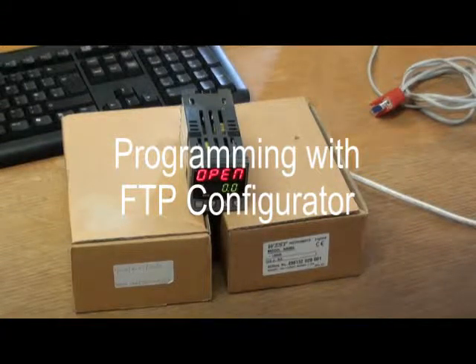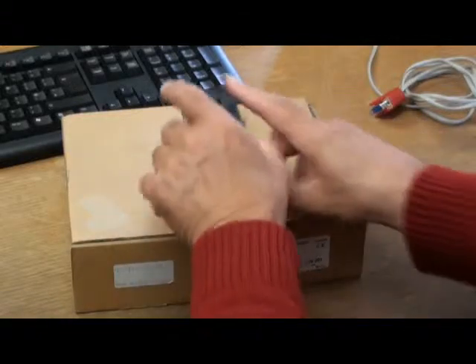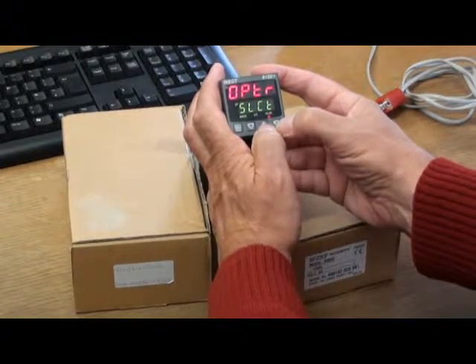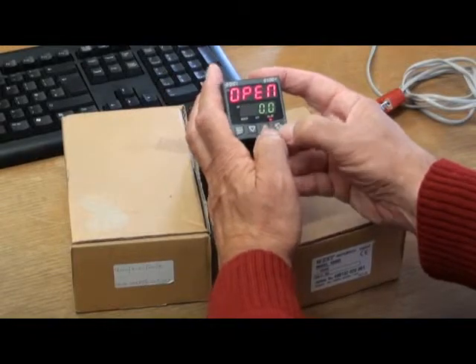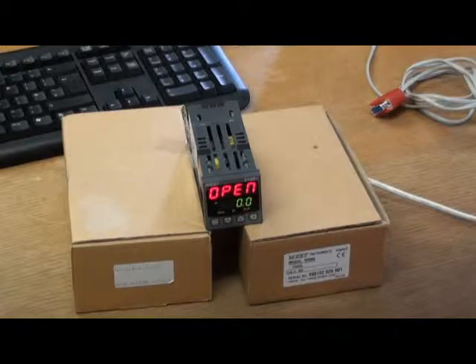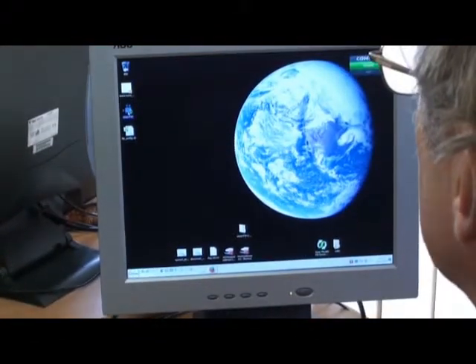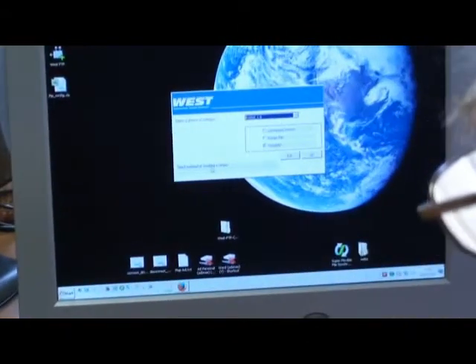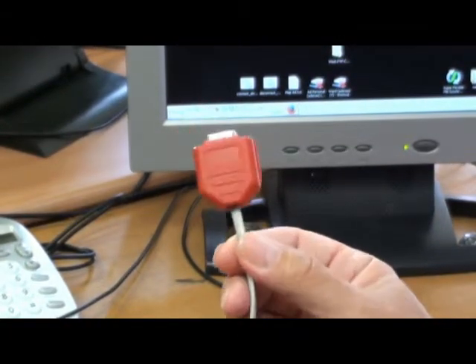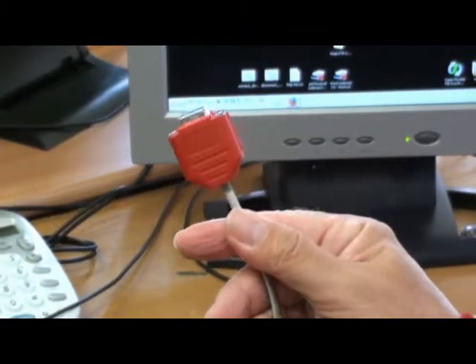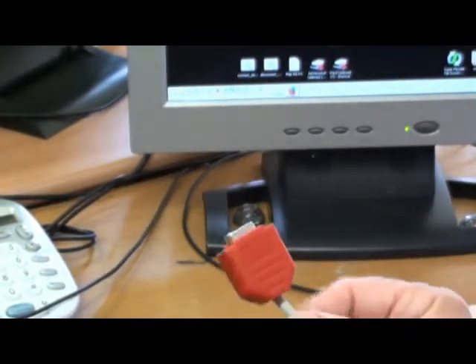As well as being able to program the Plus Series controllers from the front panel display by using the up and scroll keys to go through the various menus like setup, configuration, information, and so on, it is also possible to program them using configuration software. This comes in the form of the West Configurator software and a lead plug-in connector. Note the color of this plug-in connector is red. There are other cables for different types of instruments, and to distinguish them from each other there is a color coding for the cables. The one for the Plus Series configuration software is the red connector.